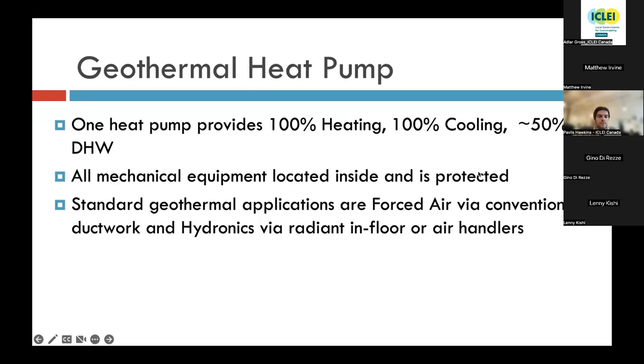Next slide, please. So a geothermal heat pump is one system or one piece of equipment that provides 100% of the heating, 100% of the cooling, and about 50% of the domestic hot water annually. Pardon me. I would point out that that 50% domestic hot water is for an average family of four, and it is seasonally biased. What I mean by that is you're going to get a whole lot of hot water contribution in the wintertime, because we live in Canada, there's a whole lot of heating runtime.